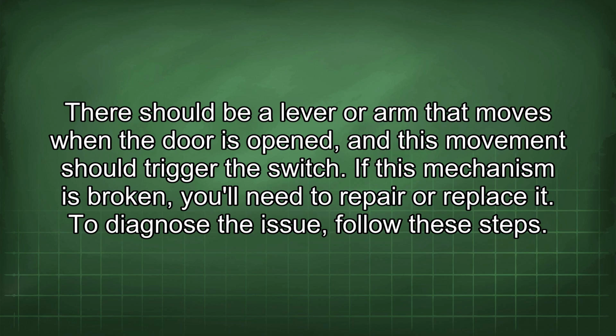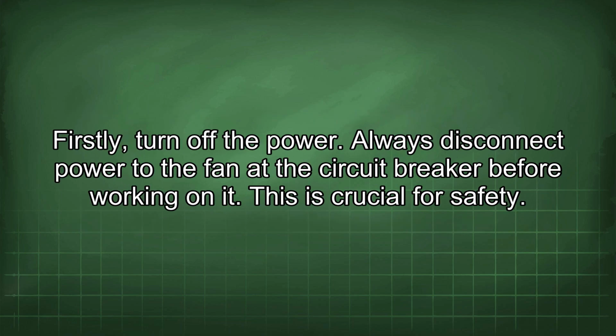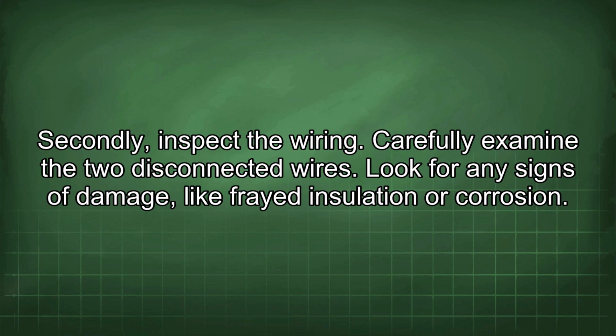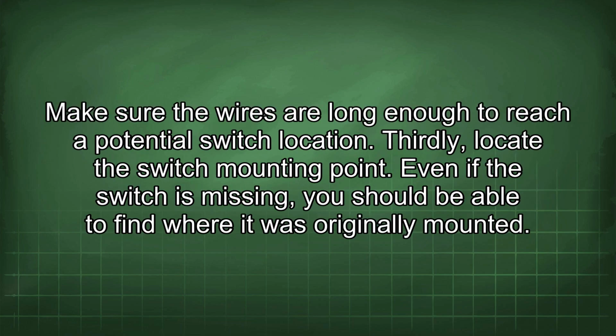To diagnose the issue, follow these steps. Firstly, turn off the power. Always disconnect power to the fan at the circuit breaker before working on it. This is crucial for safety. Secondly, inspect the wiring. Carefully examine the 2 disconnected wires. Look for any signs of damage, like frayed insulation or corrosion. Make sure the wires are long enough to reach a potential switch location.